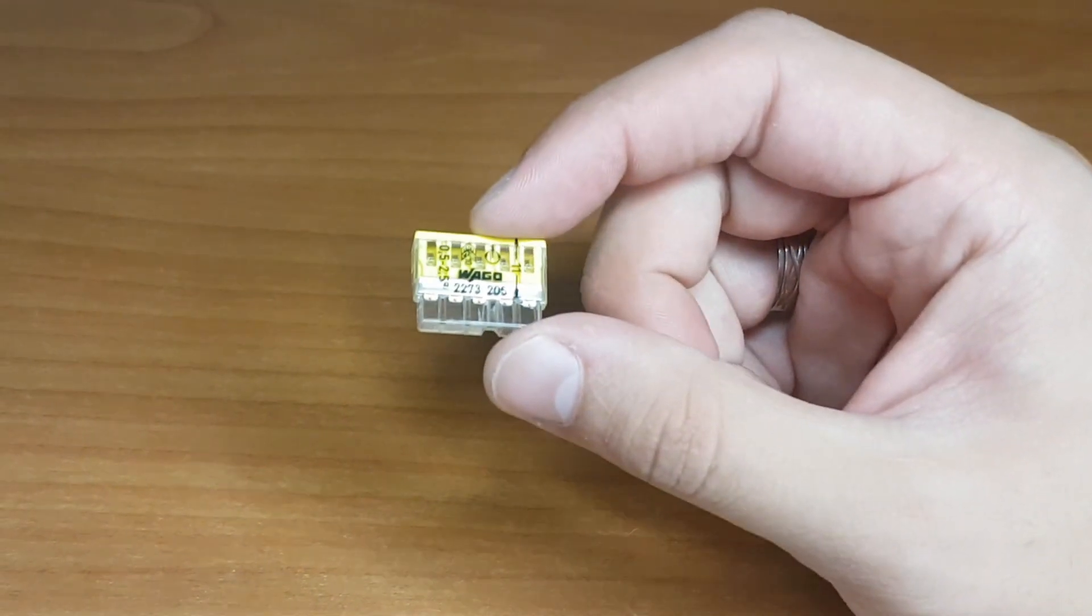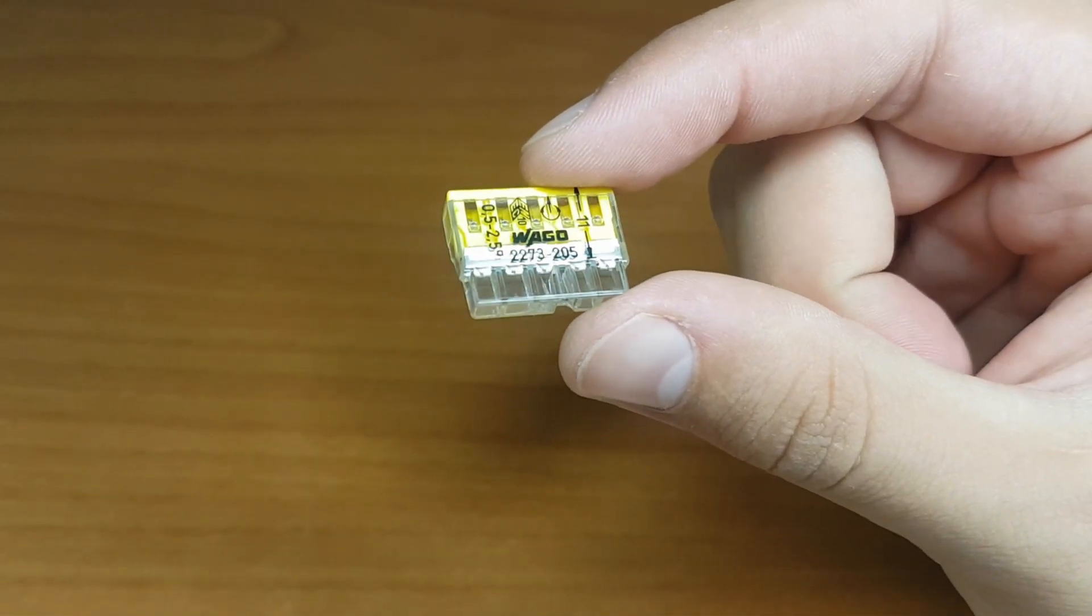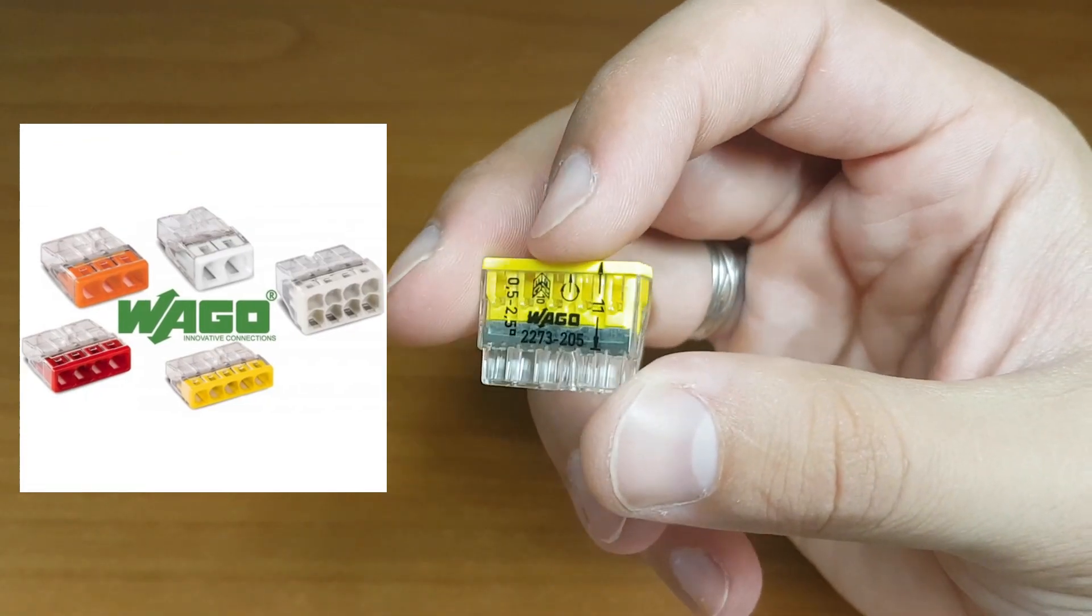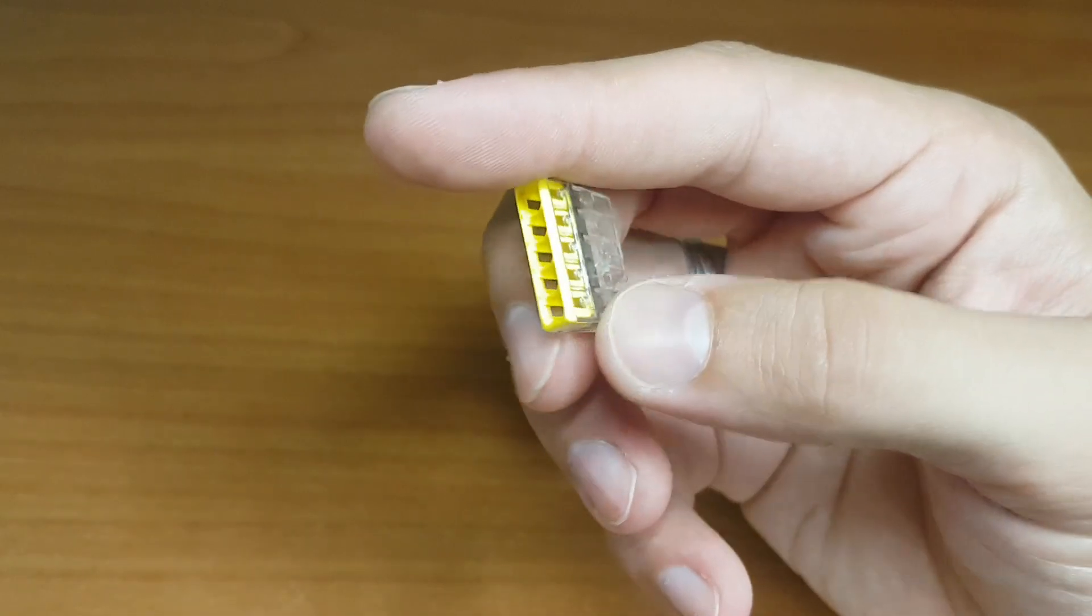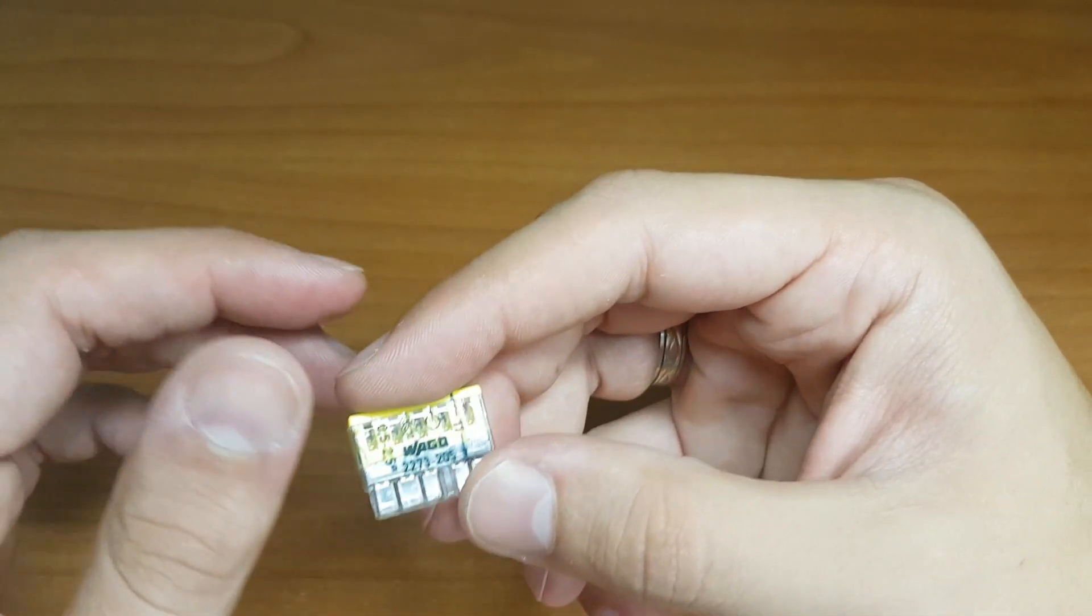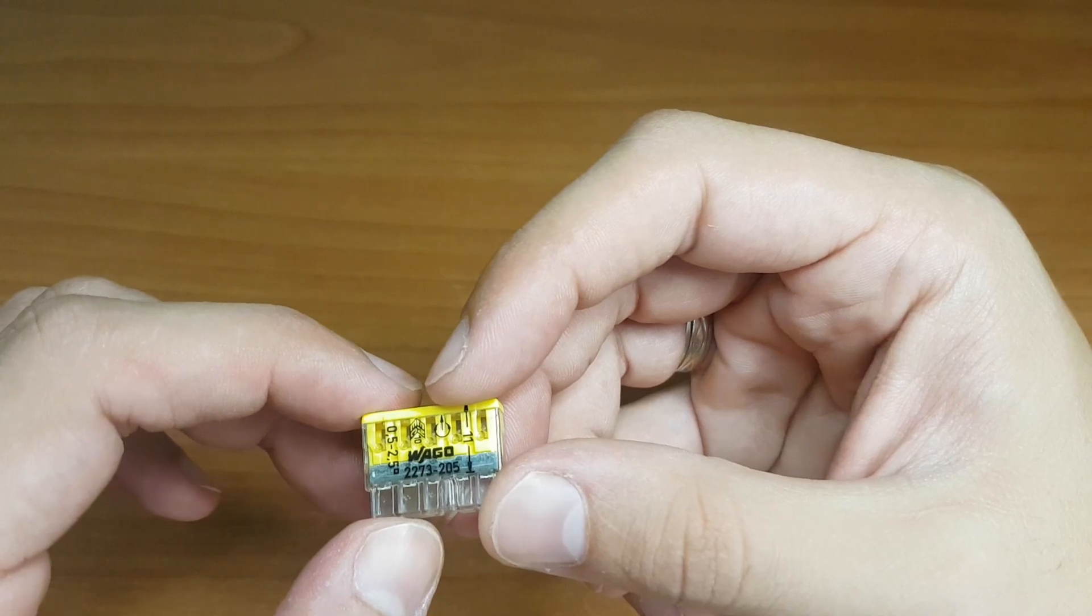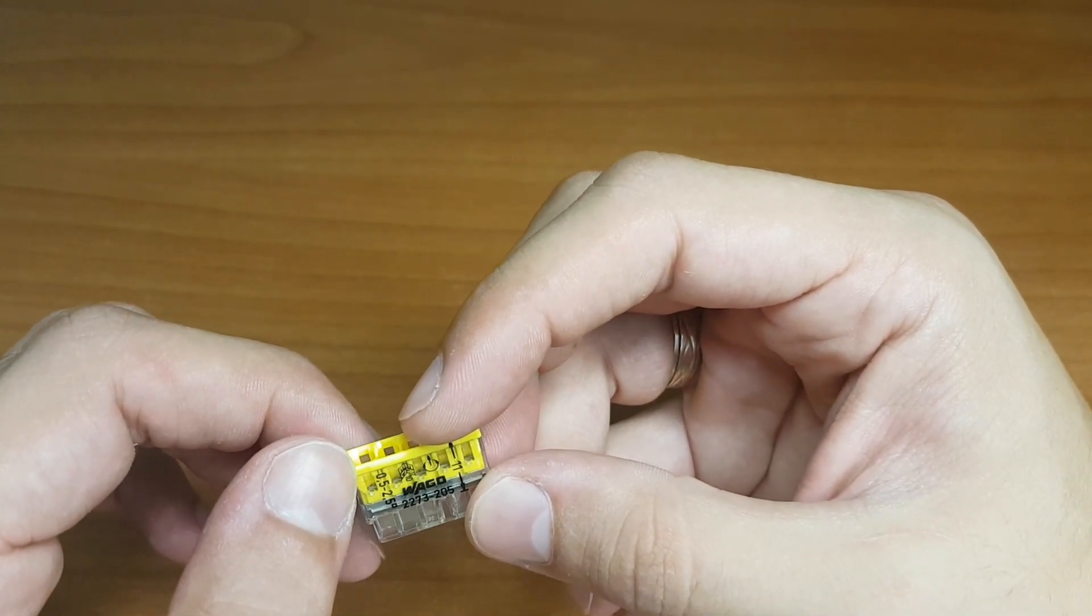First one is WAGO 2273 series. This series allows fast wiring for solid conductors. The transparent housing shows the wire is fully inserted inside and you must shorten your wires for 11 mm.